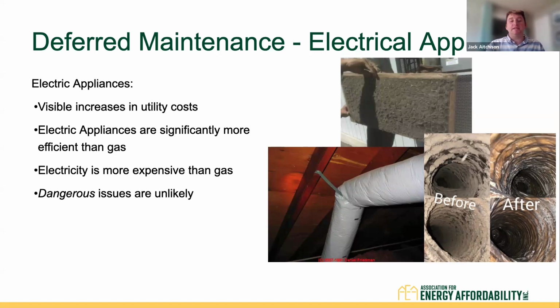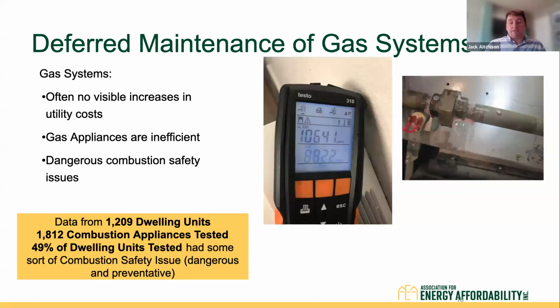In addition, you're not going to see the dangerous issues that you typically see with gas systems. Next slide, please. For gas systems, it's very different. Because they start at such a low efficiency, even if you have deferred maintenance and see a reduction in efficiency, it's not going to result in a visible increase in utilities. So if you're operating a building, you're often not going to see a significant increase in your gas usage if you have deferred maintenance on your gas system. Take a furnace, for example. If we're at an 80% efficient furnace and it goes to 65% efficient, that's a marginal increase of consumption to meet the same load. So it's not going to result in a visible increase in utility costs.